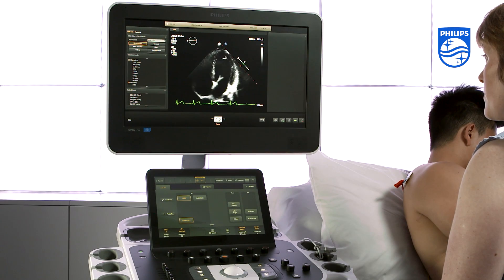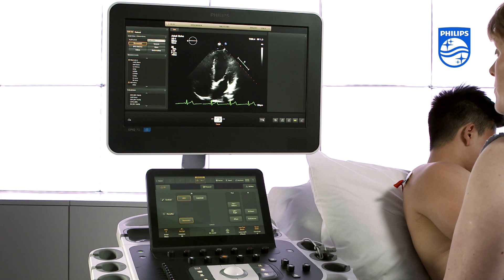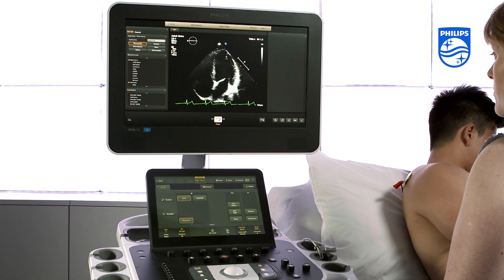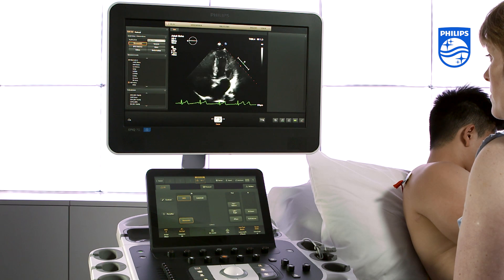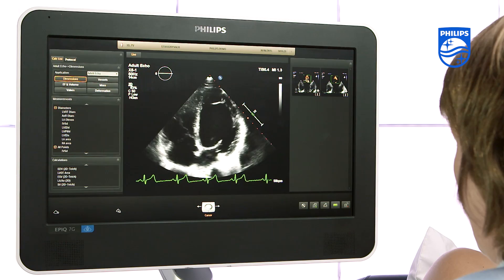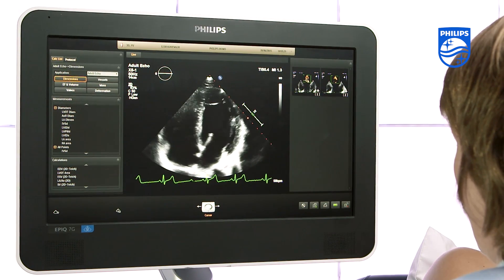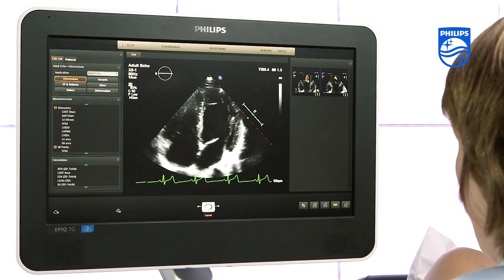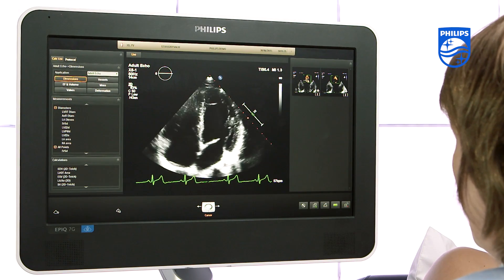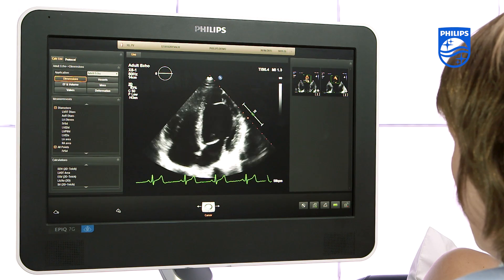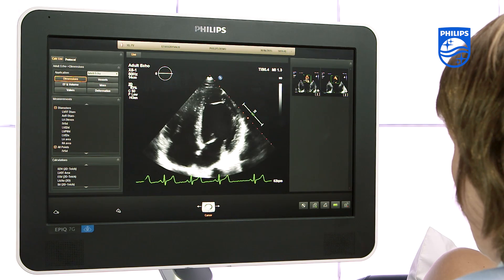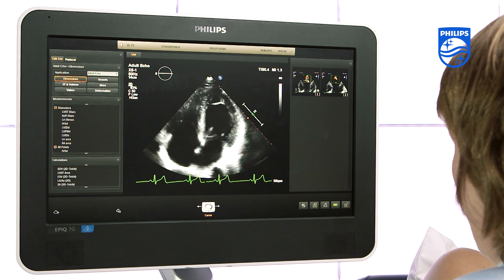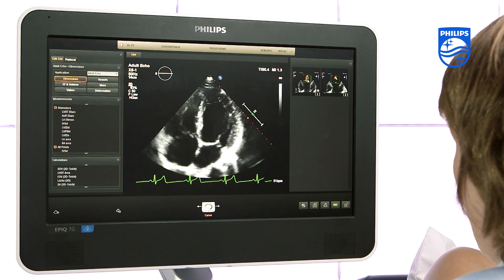Today we're going to show you how to acquire a full volume data set on the Philips EPIQ ultrasound system. We are using the X5-1 transducer, which inherits all the great features of the S5-1 single crystal pure wave transducer combined with Live3D. Here we are scanning the apical 4 chamber, but you can acquire from different anatomical views depending on your target anatomy. We use full volume when we need a larger volume of data which usually includes the whole heart — for example when you want to perform an ejection fraction in QLab.